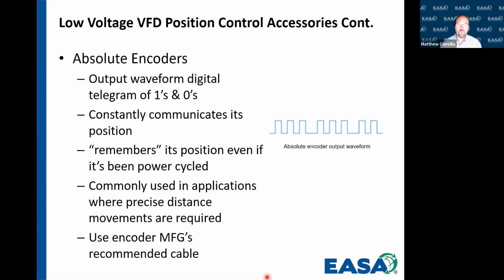So instead of waiting for a pulse for a change like we are with a resolver or for an incremental encoder, this is constantly telling the drive system what position it's at. What's really neat about these is when the absolute encoder is power cycled, it actually remembers its location. So it will tell the position that it was last in. The only caveat to that is if we lose power to the absolute encoder and the shaft is spun, we might not be in the position that was last remembered by the absolute encoder.